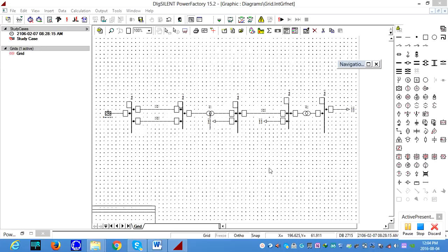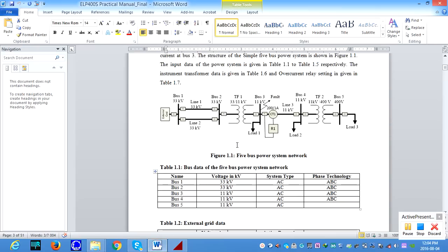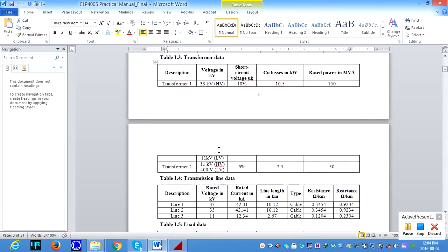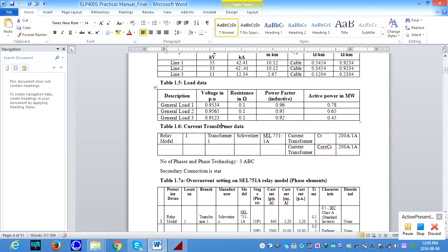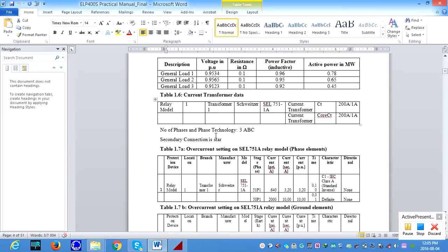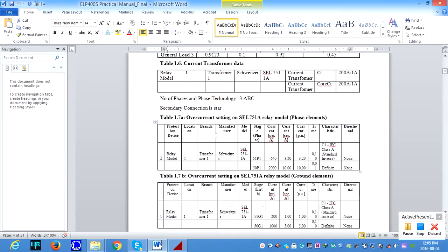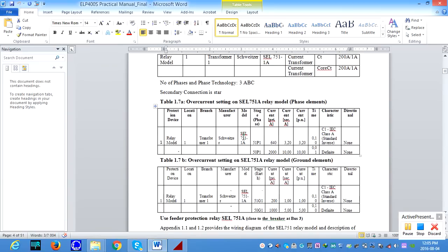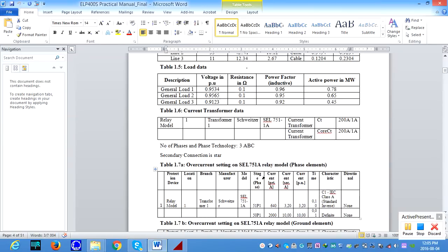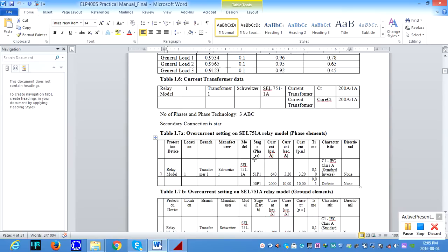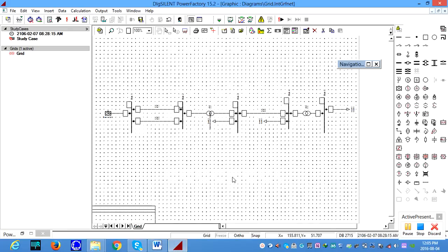Now we model the power system network in DIgSILENT, and also we change the power system component settings exactly according to the lab manual, which is given for the bus data, grid data, transformer data, transmission line data, and load data. The next part, we need to implement the protection settings, especially for the 751 relay model and the CT settings for phase and ground elements. But before we deal with these things, we make sure to conduct a load flow and validate the load flow results before we proceed to the protection setting.